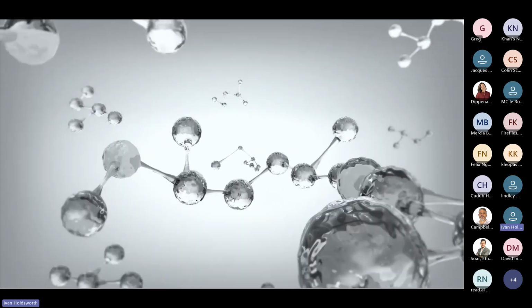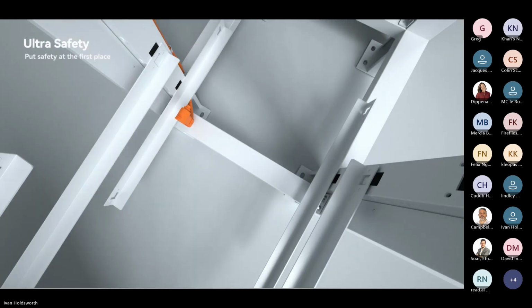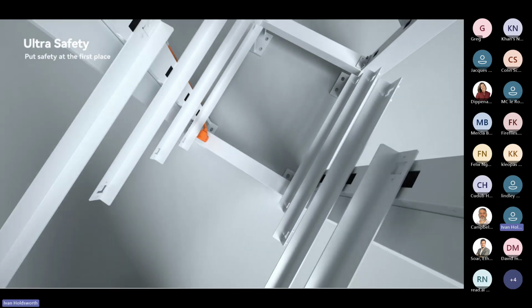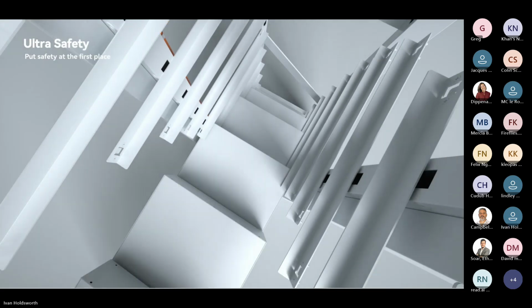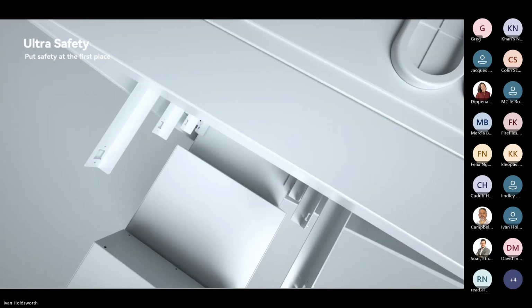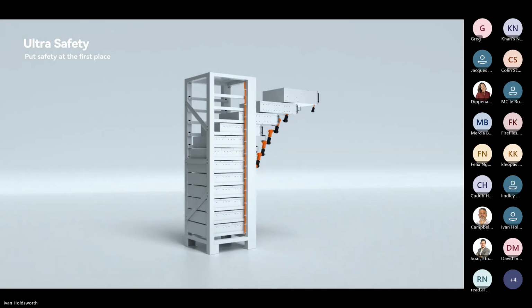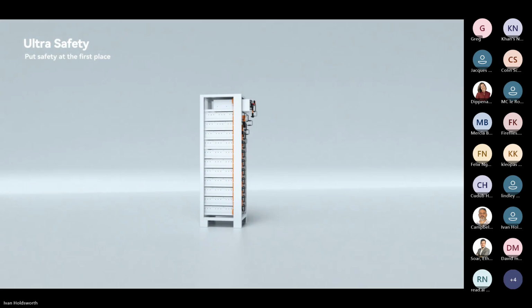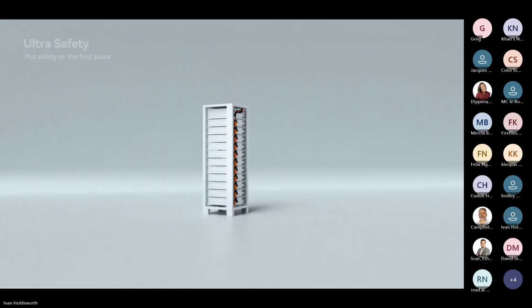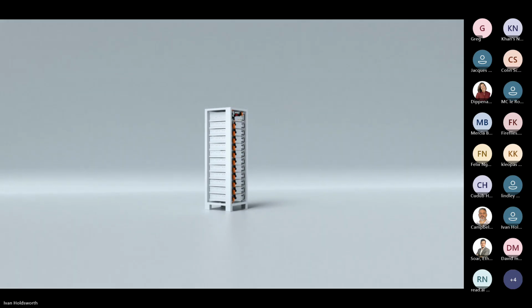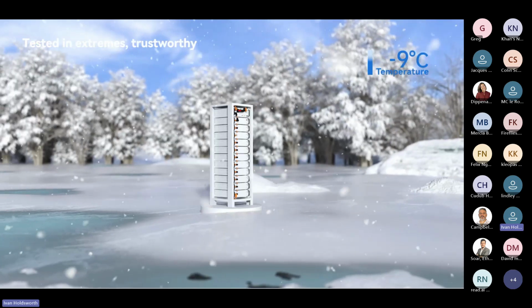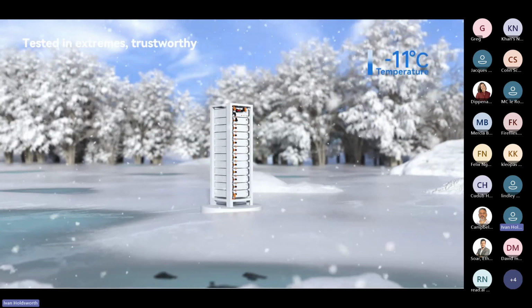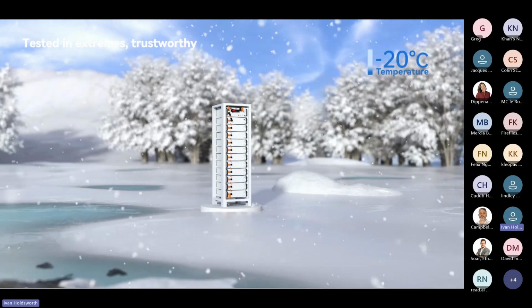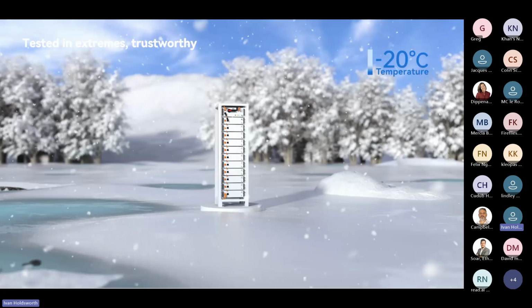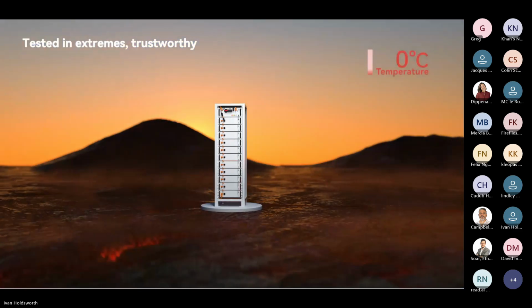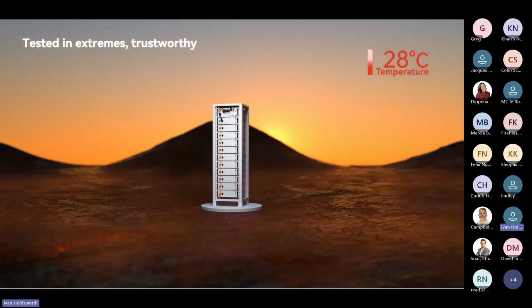BYD batteries are lithium iron phosphate, cobalt free. And here we can see the construction of the Max Lite in racks. It does have a wide operating temperature range. However, your charging and discharging will get derated in cold weather. Your charging will get derated more than your discharge. And it can operate all the way up to 50 degrees centigrade.